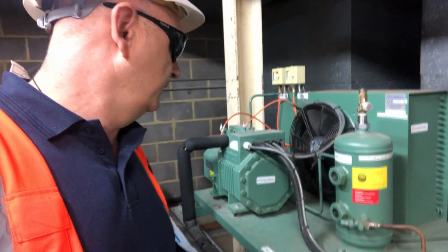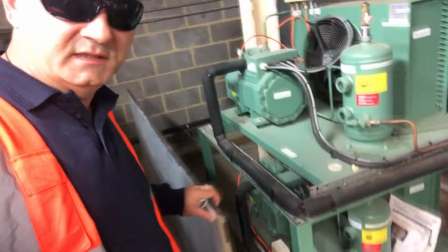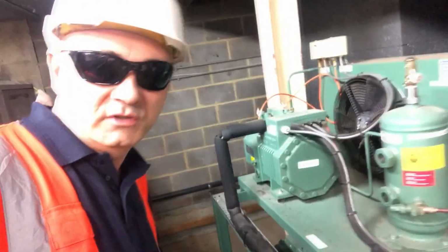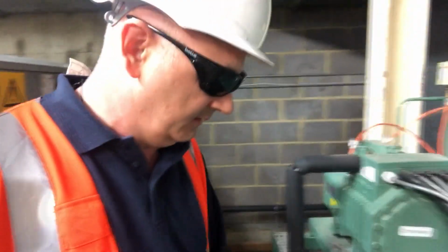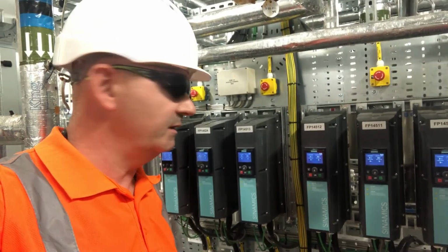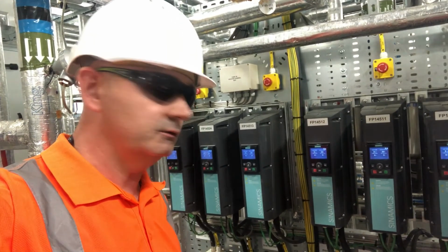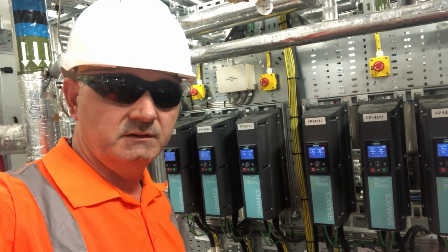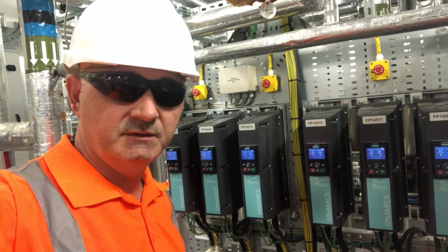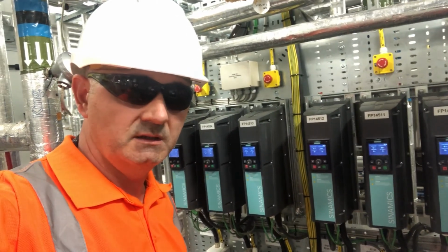As you'll see here, this is a refrigeration system, incorrectly built and fitted in the wrong location, and to make it worse, the owner of this business is using the refrigeration room like a storage room and is storing plasterboards and metal there, which block the condenser. It's the same customer who uses Siemens inverters, variable speed drives. They are also incorrectly set up, but that's another story.